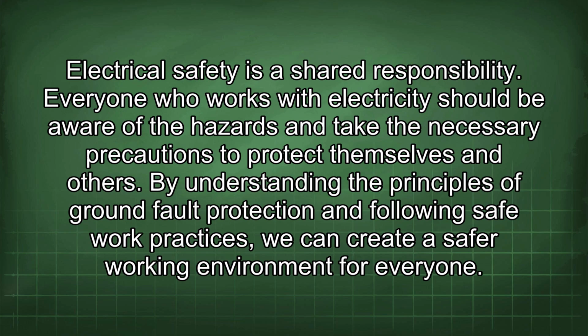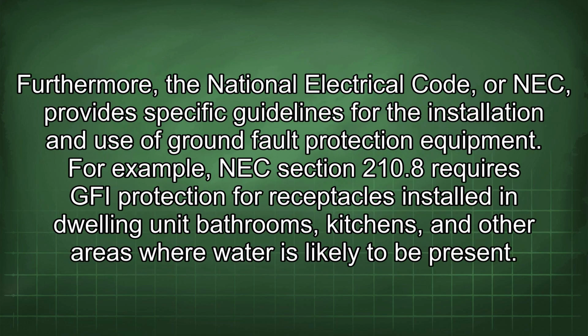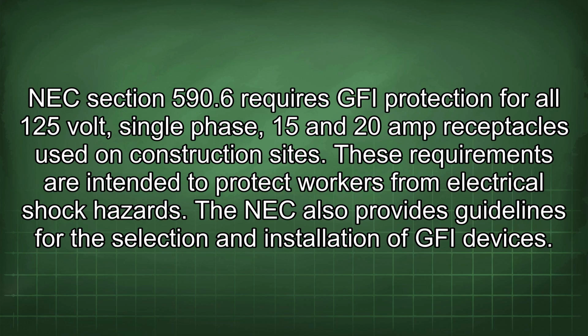Furthermore, the National Electrical Code, or NEC, provides specific guidelines for the installation and use of ground fault protection equipment. For example, NEC Section 210.8 requires GFI protection for receptacles installed in dwelling unit bathrooms, kitchens, and other areas where water is likely to be present. NEC Section 590.6 requires GFI protection for all 125-volt, single-phase, 15 and 20 amp receptacles used on construction sites. These requirements are intended to protect workers from electrical shock hazards.